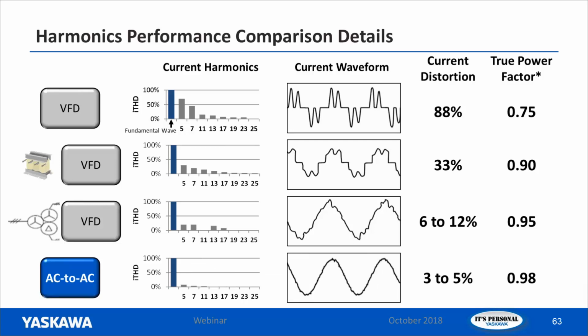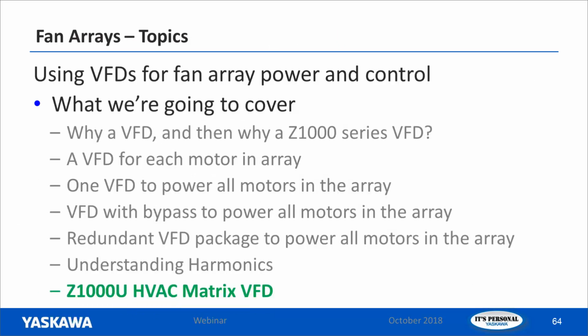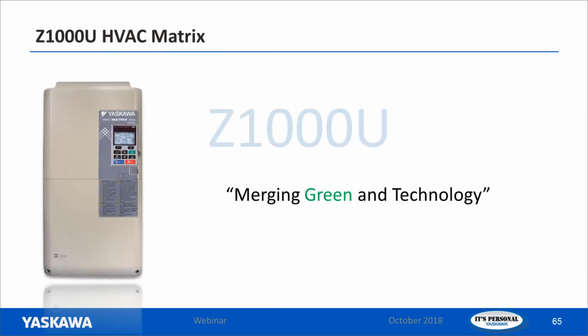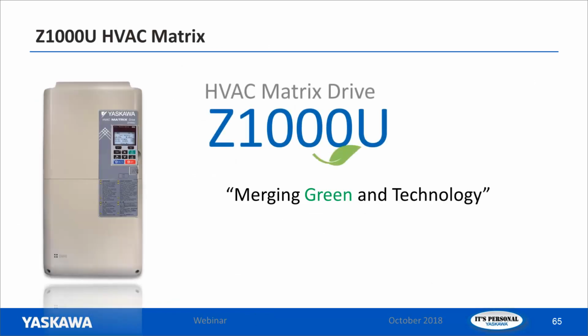Here it is. That's a pretty clean looking sine wave there. With the Z1000U drive, which is an AC to AC drive, we now can get that current distortion down to 3 to 5%, and the power factor up to 0.98. Let's look at the Z1000U HVAC matrix drive. And there she is, smiling at us.